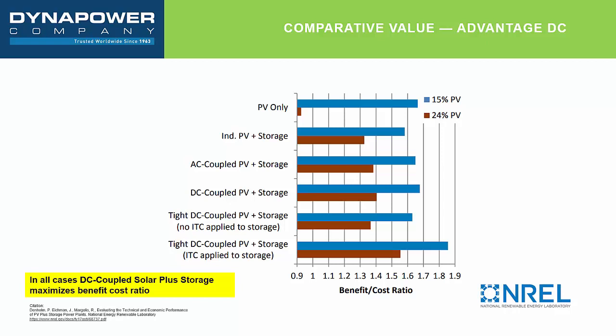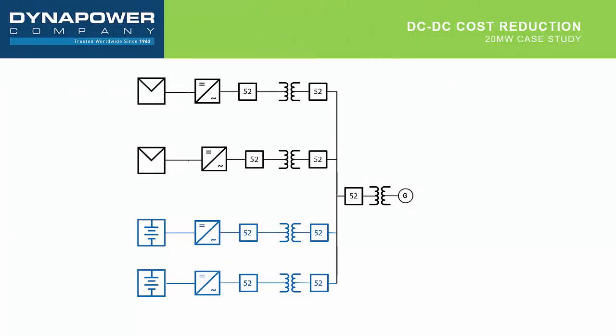This offers the advantage, of course, that you can't charge the batteries from the grid, therefore there's no chance of ITC clawback as mentioned previously. But the disadvantage now is that it removes basic arbitrage as a use case and removes frequency regulation as an ancillary services use case as well. Despite this charge limitation and the limitation on the use cases, the DC coupled benefit to cost ratio still is superior. Let's start on the cost side and try to dissect where some of these cost savings are coming from.